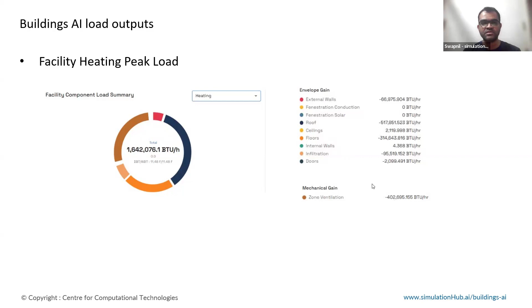We have the heating peak load coming in due to external walls, heat loads from the roof, internal gains due to infiltration, doors, as well as the zone ventilation required, and the additional heat gains due to zone ventilation. All these values and their distribution breakup are available from the tool.